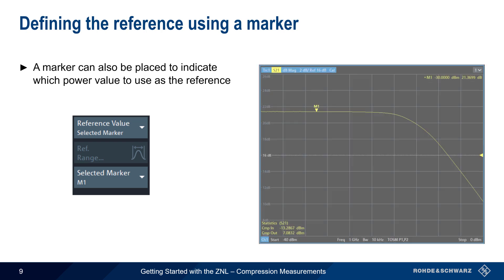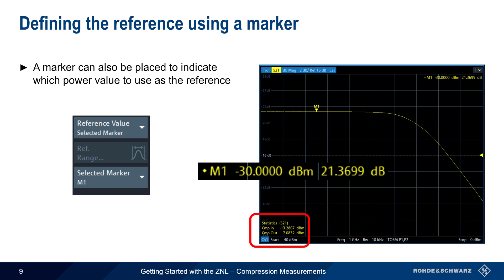The reference value can however also be defined in other ways. For instance, the user can place a marker on any arbitrary point on the trace, and this point will serve as the reference value for the compression point calculations. In this example, a marker has been placed at the point on the trace corresponding to an input power level of minus 30 dBm. The input and output compression points are now calculated using this user-defined point as the reference value.